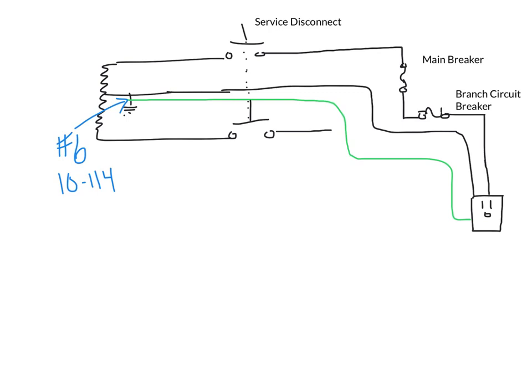Let's take a look at our circuit here and introduce a fault into the system. Let's say maybe that receptacle has a loose screw and it wiggles a bit and shorts out against the side of the box. Where's fault current going to go? Fault current wants to go back to the source, and bonding provides a path for it to do so. So when we follow that fault current path back to the source, we get back to the XO point on our transformer, and some of you are probably thinking at this point, well, fault current goes to ground.